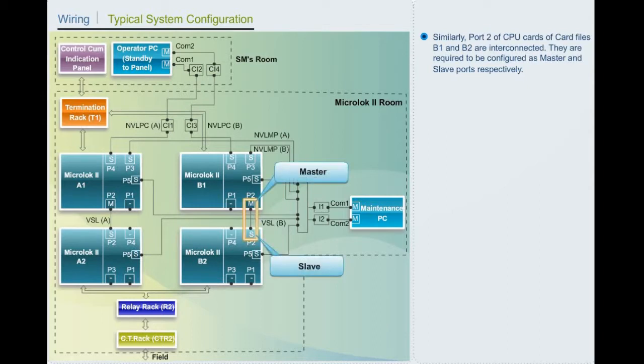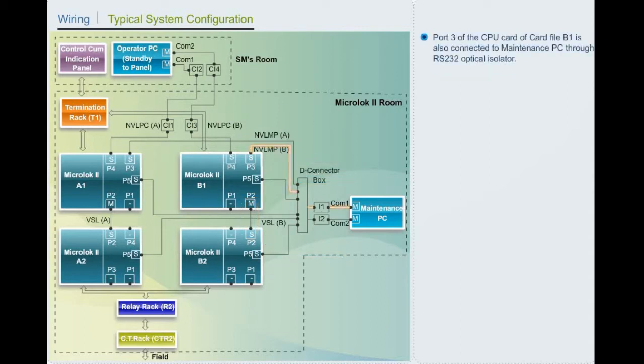They are required to be configured as master and slave ports respectively. Port 3 of the CPU card of card file B1 is also connected to maintenance PC through RS-232 optical isolator. Port 4 of the CPU card of card file B1 is connected to the RS-232 port of the VDU panel through RS-232 or RS-485 converter cum isolator connected at either ends. Port 5 of CPU card of any card file is connected to the maintenance PC for debugging purpose.